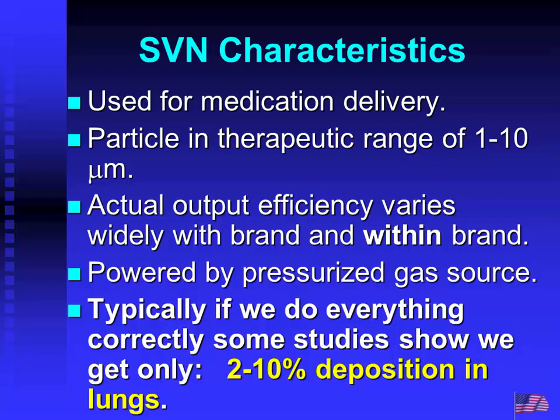Typically, the particle size is in the therapeutic range of 1 to 10 microns. Sometimes it gets a little more specific. Ideally, where we want it for deposition in the airway is 2 to 5 microns, so it's well within that range. The actual output varies widely, even within a brand. In other words, there's no standardization, even within the same lot.